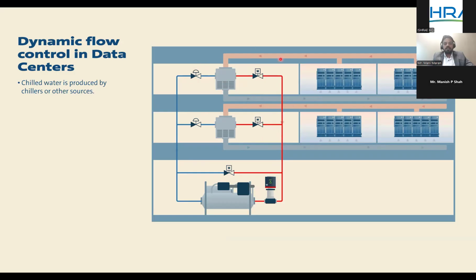And we capture the differential pressure, the back pressure created by the valve when it is moving up and down, and that feedback is given back to the centralized pump, and the flow is being modulated. So if there is more load, the valve opens, and the differential pressure goes high, and that feedback is given back to the pump to increase the flow. And vice versa, when there is less load, the valve closes and the back pressure varies, and that feedback is given back to the pump to reduce the flow. It's a pretty simple system. That's how we operate a variable primary system or variable secondary system.